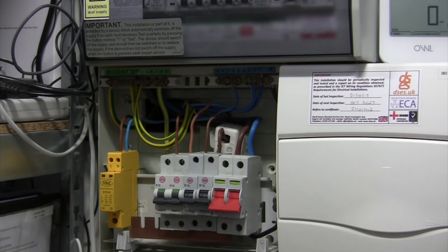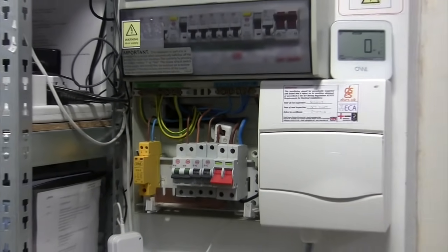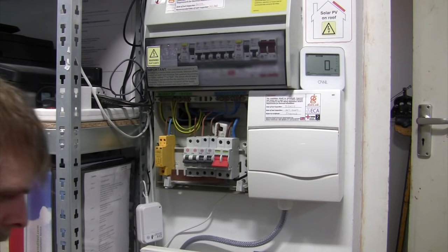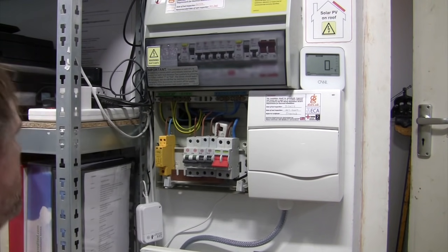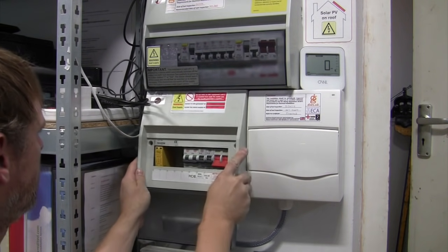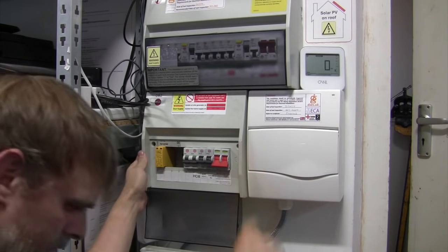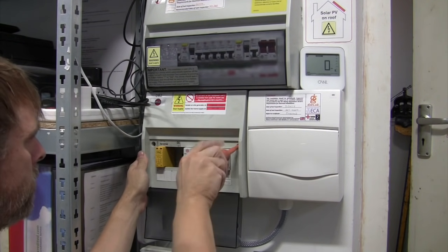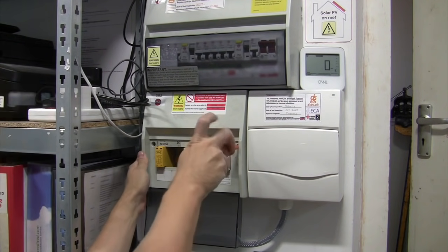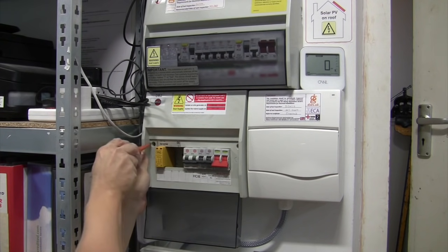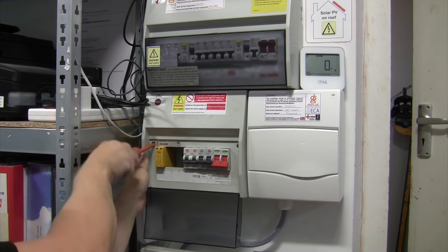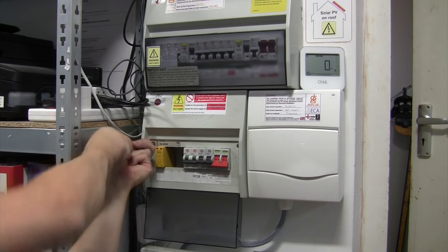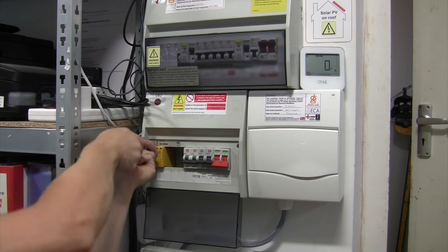There we go, installation is as easy as that. I've got a 6mm protective earth there and 2.5mm on the line and neutral cabling. How do I know it works? Well, I don't. There's no way for me to reliably test it. In fact, I'll have to periodically visually check it to ensure the indicator windows still show it as being functional. Some models come with an audible alarm or with contacts to connect to such, but not this one.